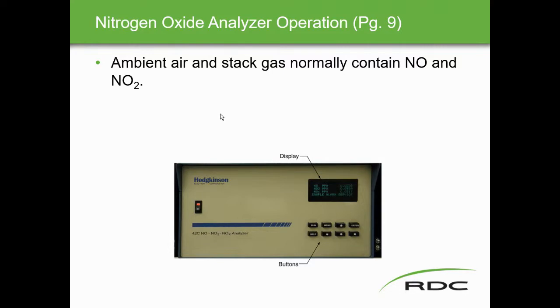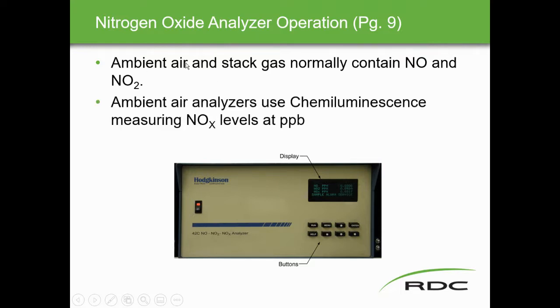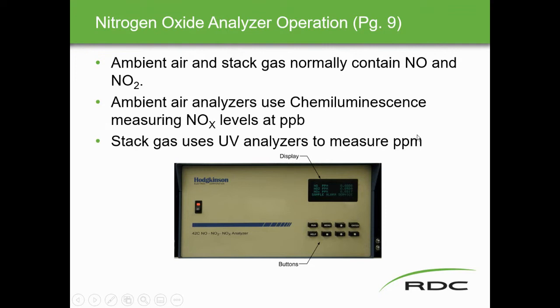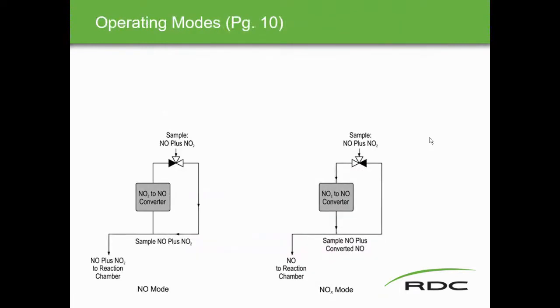To summarize the measurement modes: when measuring stack gas, UV analyzers are used for parts-per-million concentrations. When measuring ambient air, chemiluminescence is used because it can reach down to parts-per-billion levels. These two techniques — UV for stack gas and chemiluminescence for ambient air — complement each other for NOx monitoring.